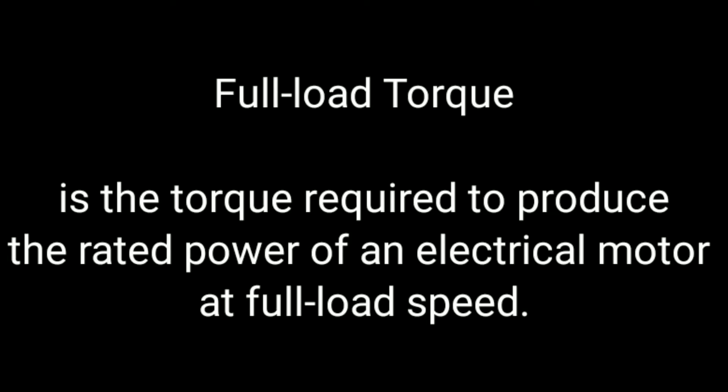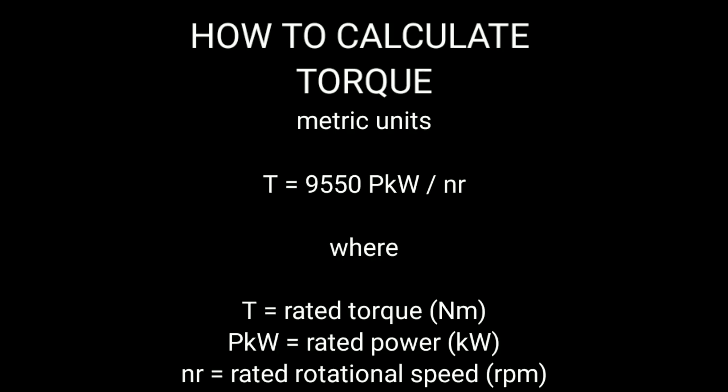Fourth, full-load torque is the torque required to produce the rated power of an electrical motor. To calculate torque in the imperial system: torque equals 5252 times motor HP divided by motor speed. In metric units: torque equals 9550 times motor kilowatts divided by motor speed.